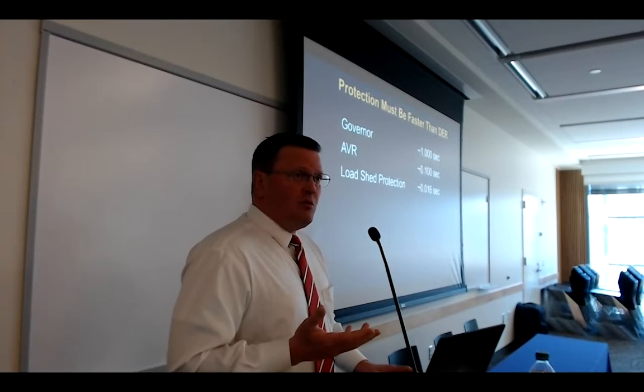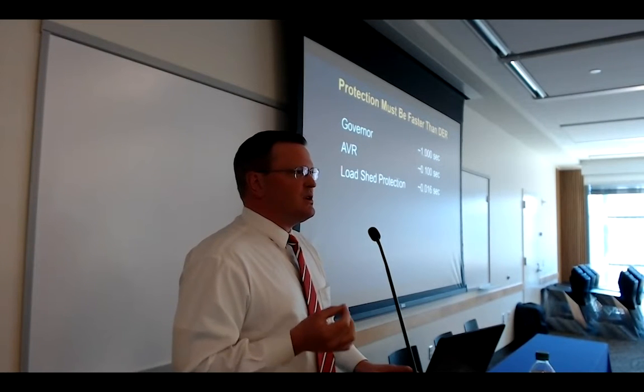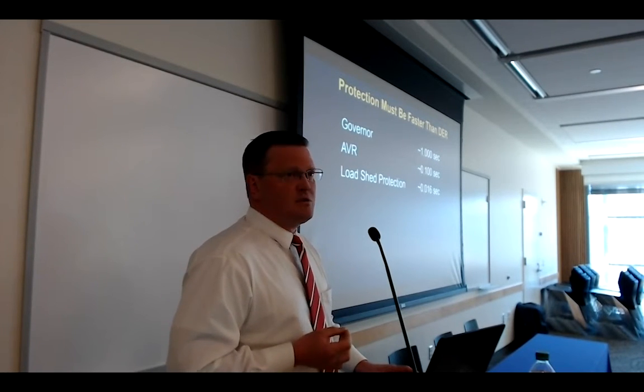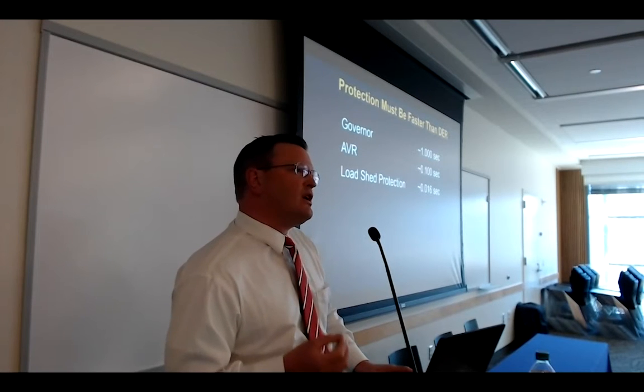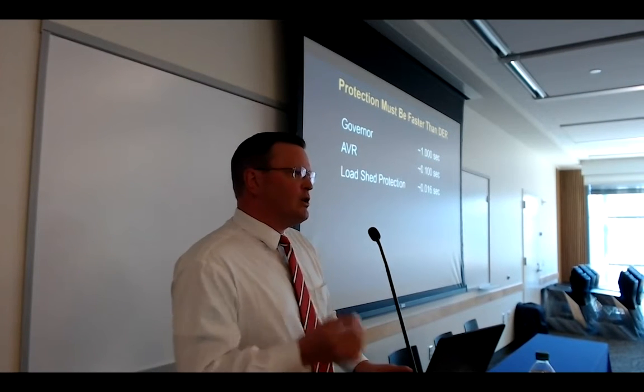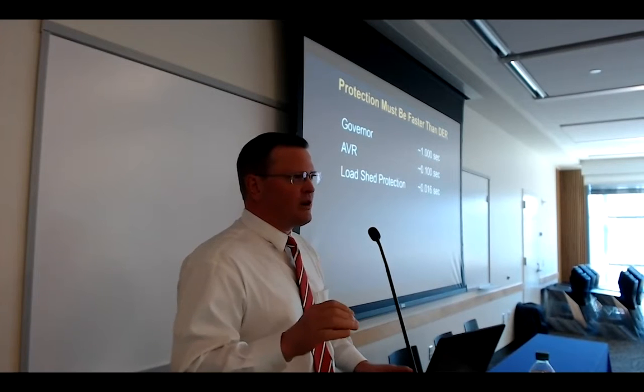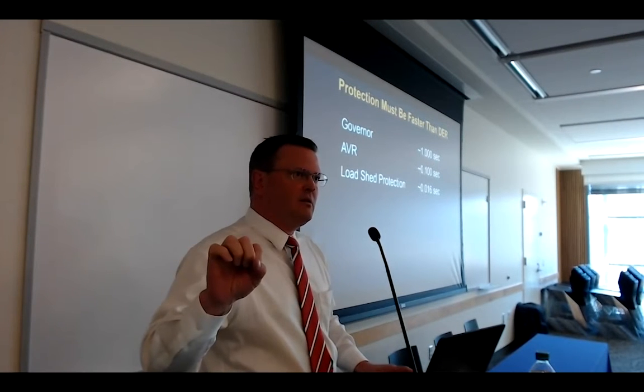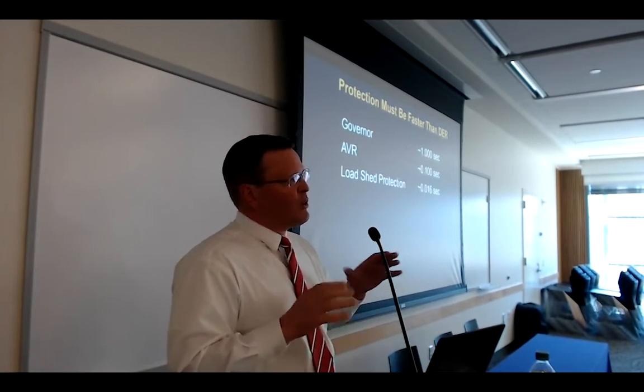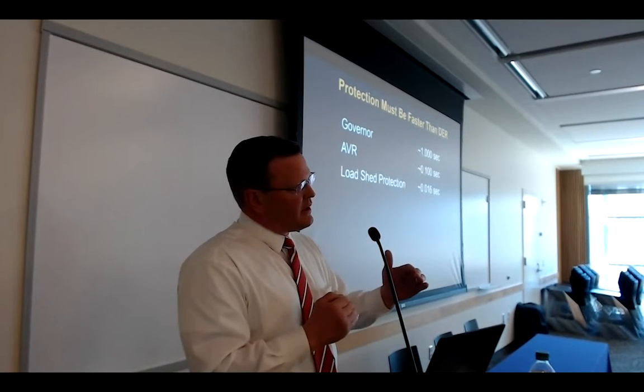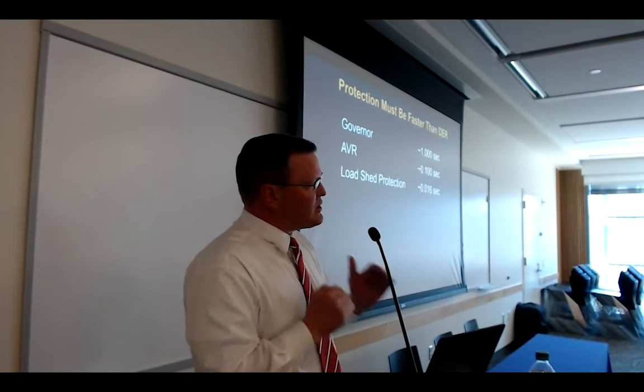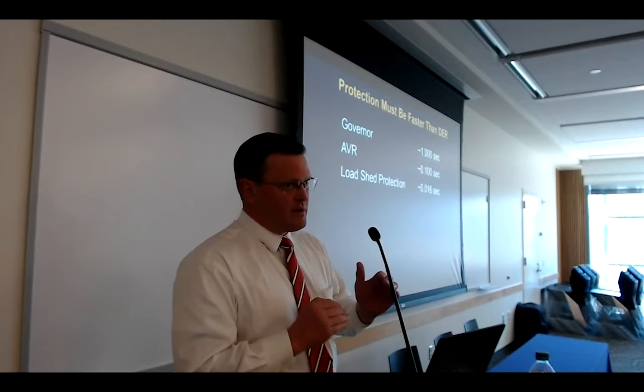Load shedding, as I showed before, makes decisions in approximately 1 power system cycle. So before the AVR can react to a load mismatch, load shedding has already made a decision, contacts are closed, solenoids are already moving. This matters because it's a time scaling designed over 100 years that we must not corrupt.